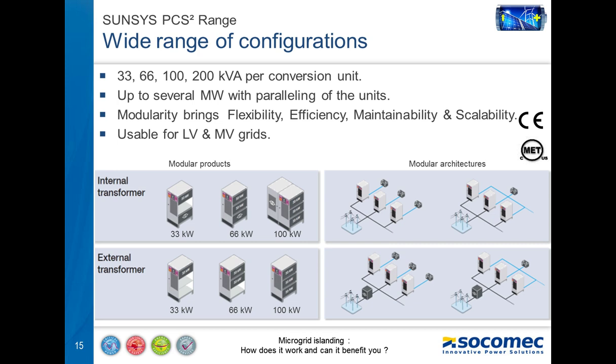These units can be put in parallel in order to reach several megawatts applications. And they are modular. They are composed of 1, 2, 3, or 6 modules of 33 kVA. And the architectures can also be modular with one transformer per unit, for example, or one single transformer for all the units in parallel. This gives more flexibility to the installation. It also increases the efficiency, the maintainability, and the scalability. All of this makes it possible to use our products for low voltage, but also for medium voltage grids.